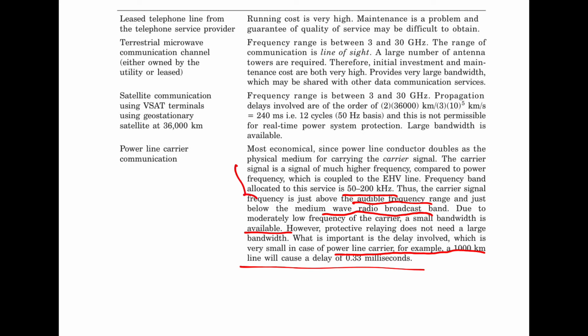And the frequency band allocated in this case is 50 to 200 kilohertz, and the carrier signal is just above the audible frequency and below the medium wave, that is the MW radio broadcast band. It also has a small bandwidth, because for protection a large bandwidth is not required. So the delay involved is very small in that case. That is a very important part.